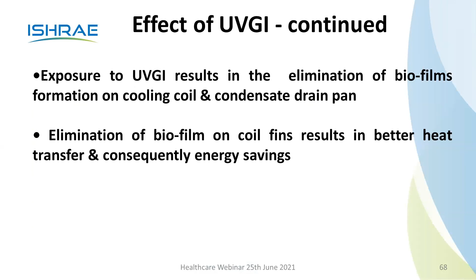Exposure to UVGI results in elimination of biofilm formation on the cooling coil and the condensate drain. Elimination of biofilm on cooling coil fins results in better heat transfer and consequently energy savings. The resultant air circulation is conducive to occupants' well-being.